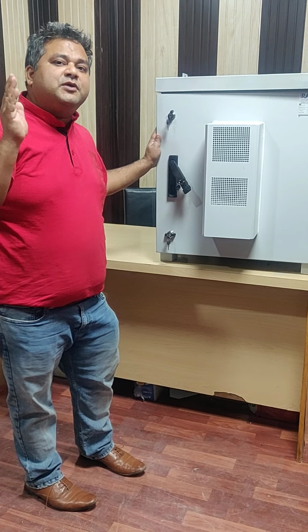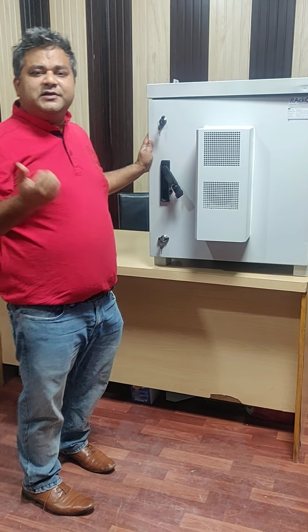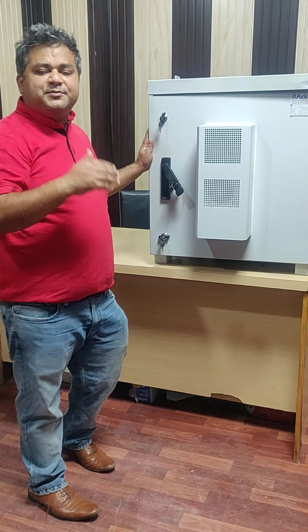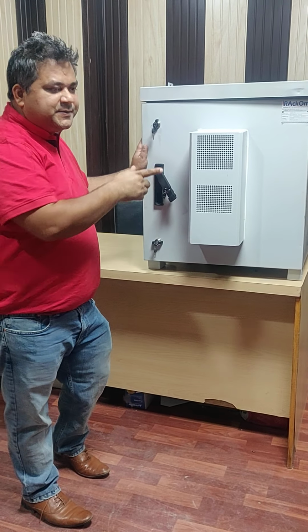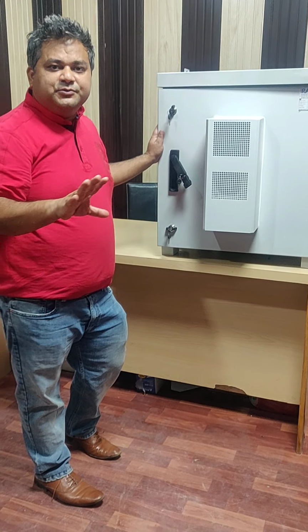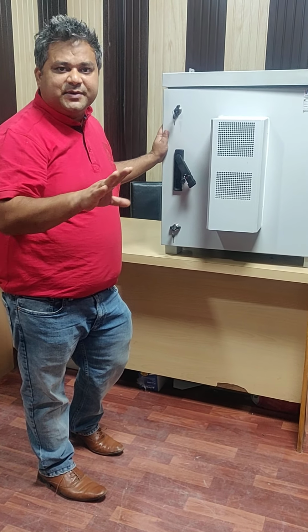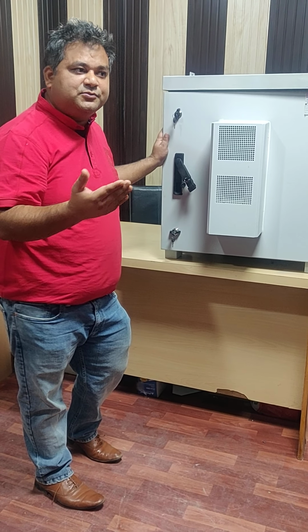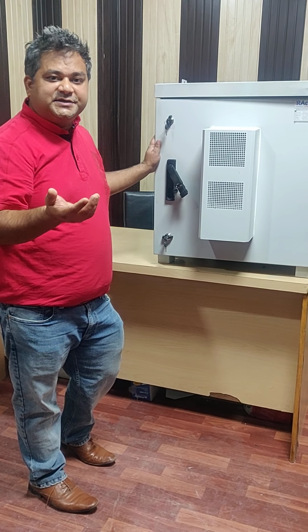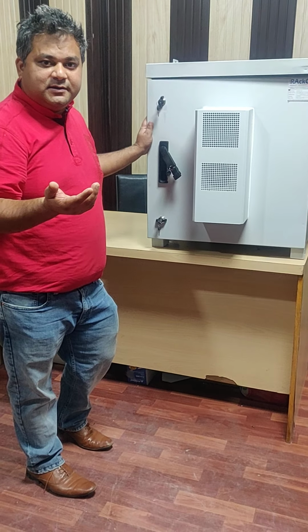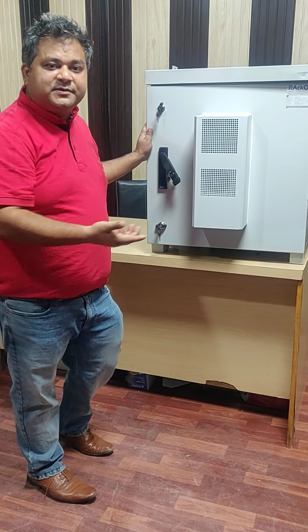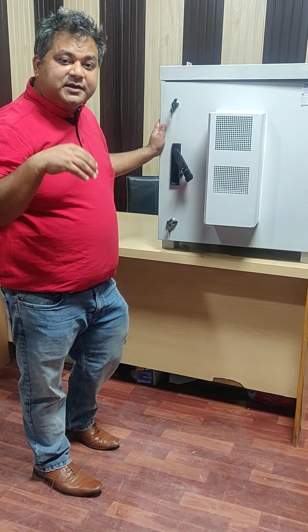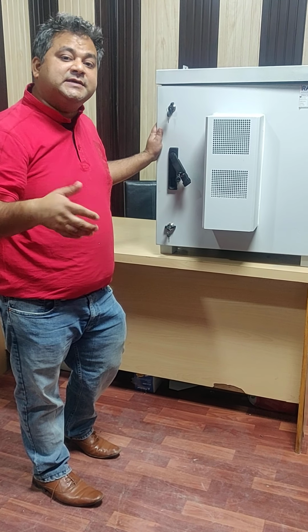And maximum you can go to 18U, 24U, 30U, depending upon the heat load, because we calculate the BTU and all these technical parameters to recommend the proper air conditioning and proper cooling inside the cabinet. It depends upon your number of equipment, the wattage, the heat load, and everything matters.